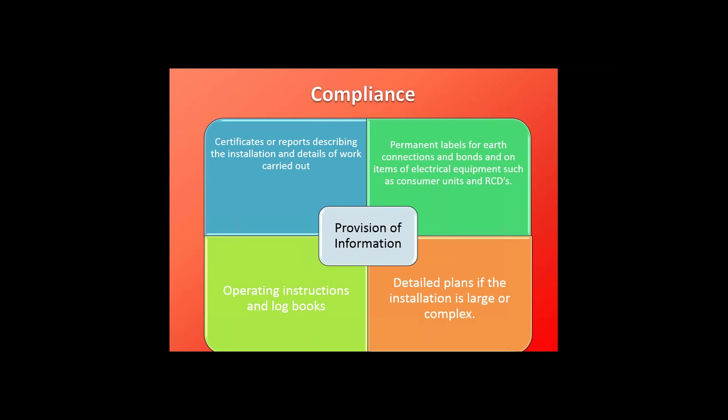When we get to the end of the job and are looking at compliance, part of the requirement now is to make sure that sufficient information is passed on to the end user of the property. All certificates relating to the work and details of the installation must be passed on. Where we have earth bonding and the like, the consumer unit must be clearly labelled — the circuits on the consumer unit should be clearly labelled so it's absolutely clear which fuses or micro switches control which circuit. Any operating instructions or logbooks also have to be left with the end user of the property.